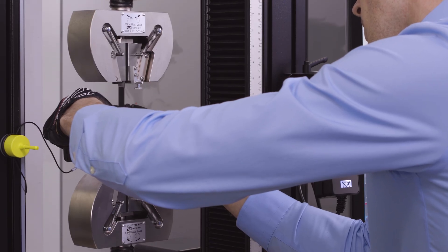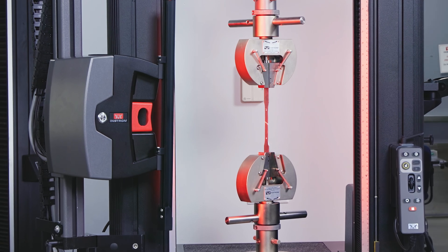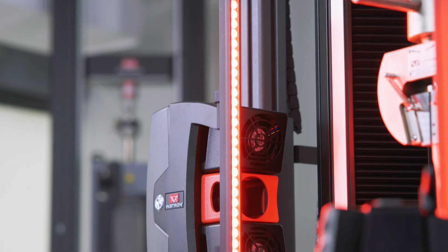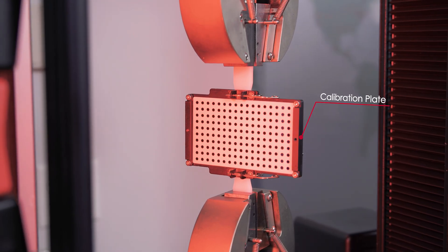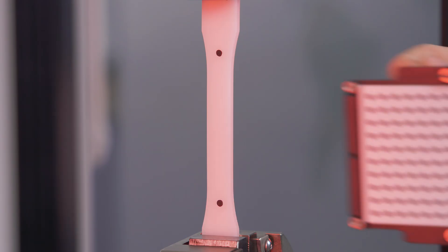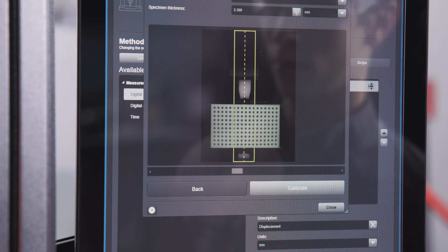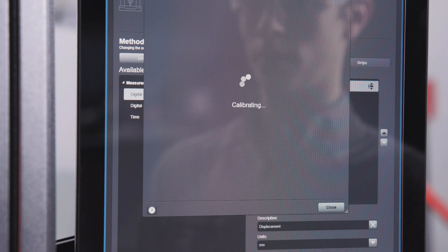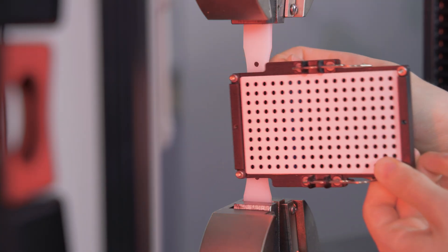There's no cumbersome attaching prior to testing, and strain can be tracked through failure without risking damage to the device. The AVE-3 is factory calibrated and shipped with a new simplified calibration plate that can clip directly onto the specimen with the load string intact.